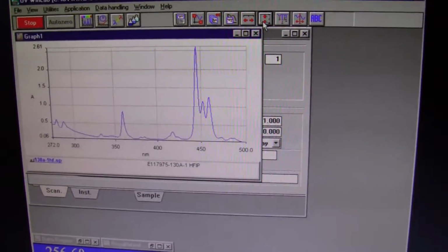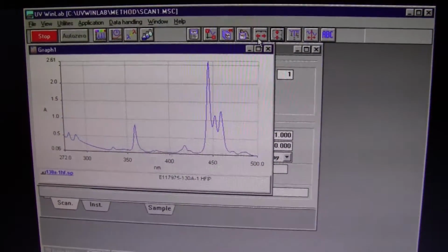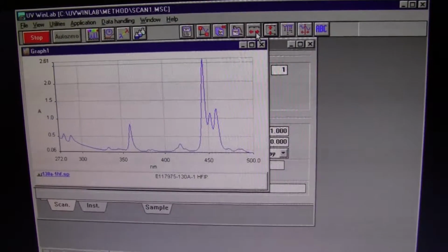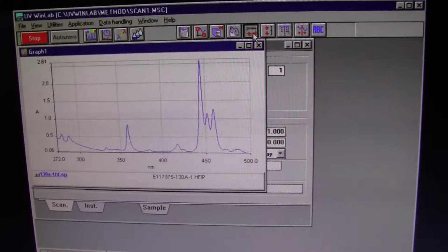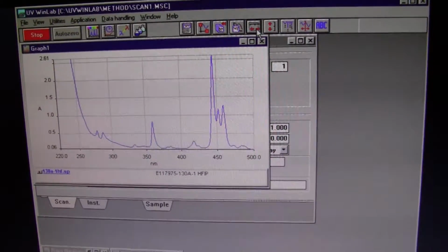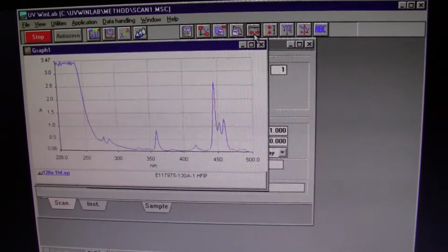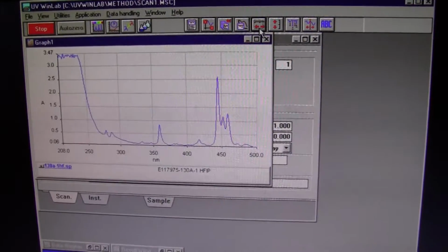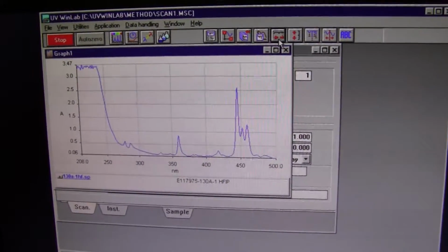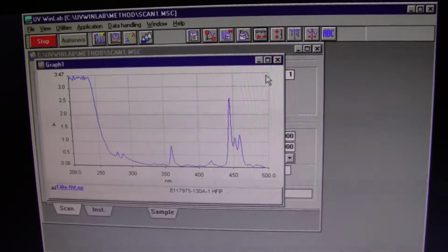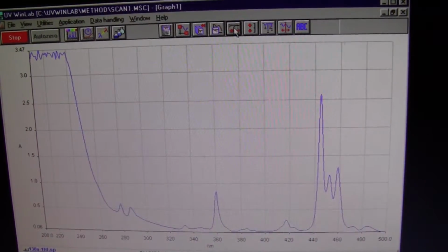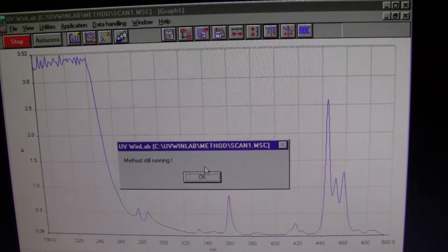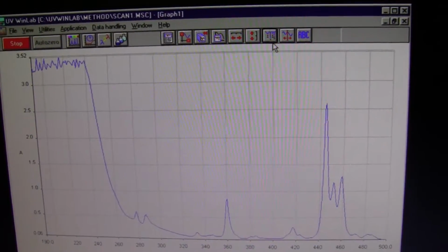And we're into the lower range now. And your three holmium peaks, standard. It's going off scale, as expected. And there we go. So there's our data set. I'll add the data points. Oops, that's still running, excuse me.